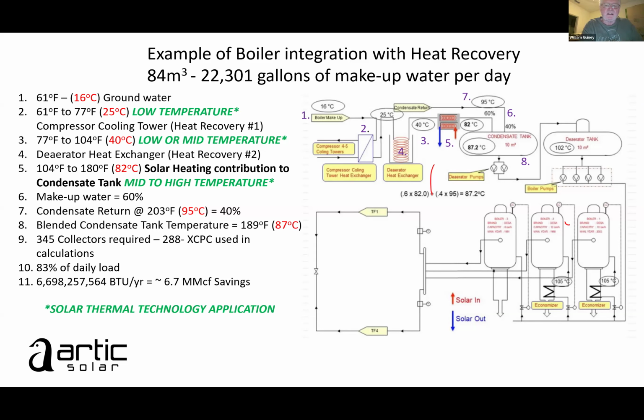So we're taking groundwater temperature, we're doing heat recovery. In this case, 2 different systems are providing preheating of that water coming in from the ground. And then it's going into a heat exchanger whereby the solar is increasing it significantly. And what we do is blend both the fresh water that has been preheated and the condensate return to come up with the average temperature in the condensation tank. So these systems are really not that complicated.